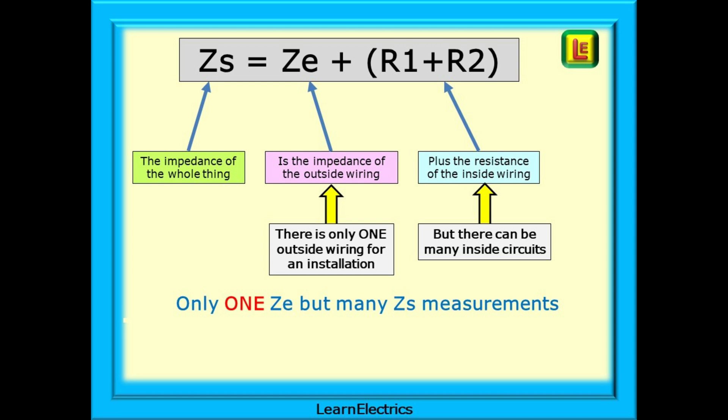You will be familiar with this formula but let's have a recap. Zs is equal to Ze plus R1 plus R2. Zs is the impedance or resistance of the whole socket circuit. It is a measurement from the point of use out of the property to the supply transformer and back. We call this the earth fault loop impedance.